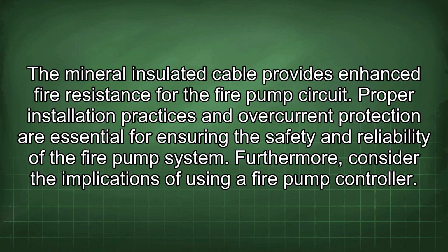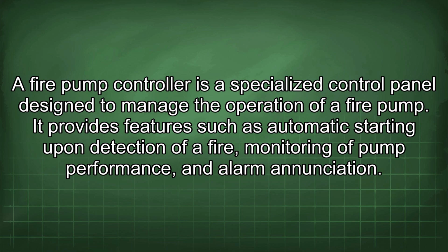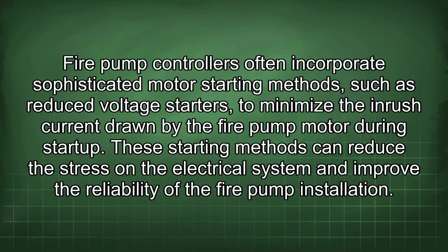Furthermore, consider the implications of using a fire pump controller. A fire pump controller is a specialized control panel designed to manage the operation of a fire pump. It provides features such as automatic starting upon detection of a fire, monitoring of pump performance, and alarm annunciation. Fire pump controllers often incorporate sophisticated motor starting methods, such as reduced voltage starters, to minimize the inrush current drawn by the fire pump motor during startup. These starting methods can reduce the stress on the electrical system and improve the reliability of the fire pump installation.